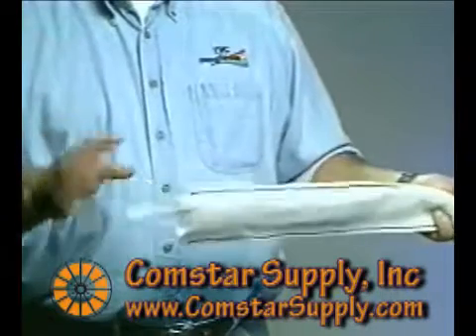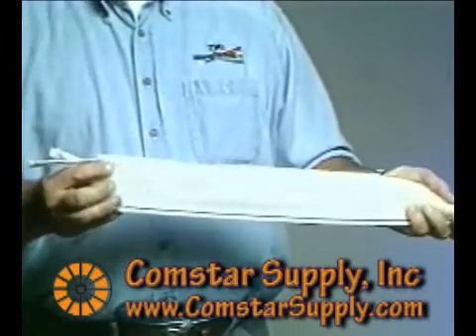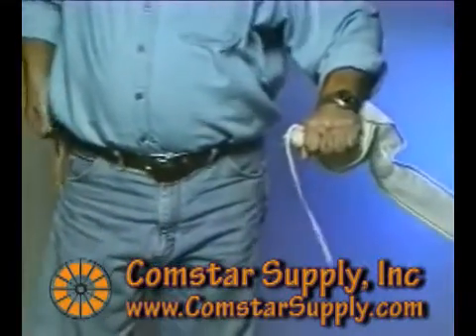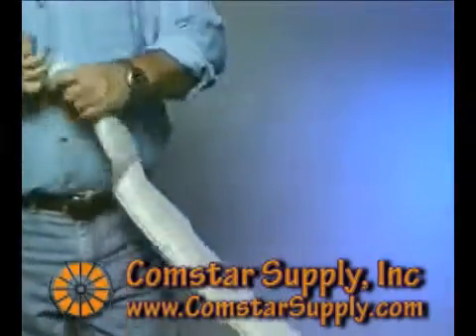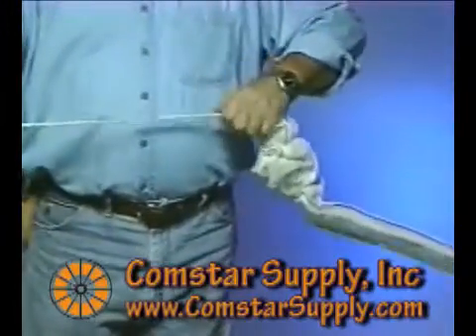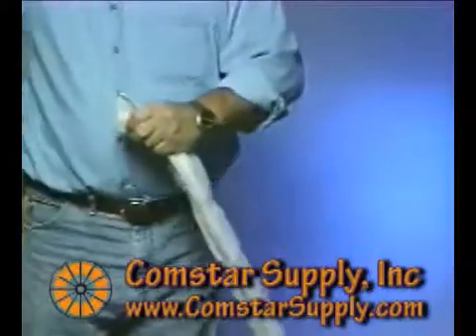This is our recommended technique to prepare MaxCell for pulling into your conduit structure. First, find all three pull tapes in your MaxCell. Then, grab each tape individually and hold and pull back MaxCell so that you can cut off 18 inches to 24 inches of tape in each cell. This will allow the pull tapes to float behind your pulling grip when pulling in MaxCell.